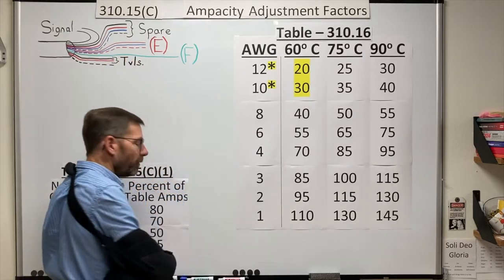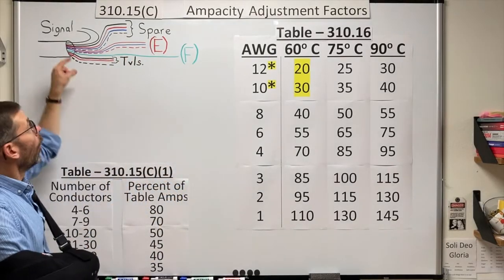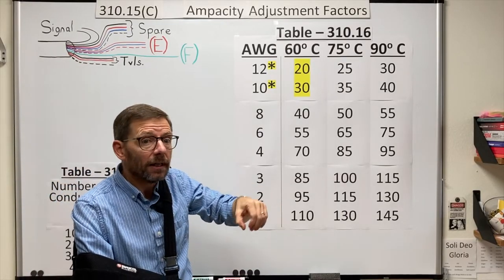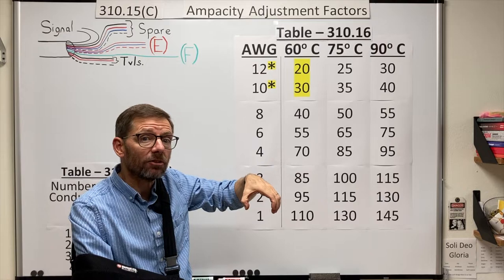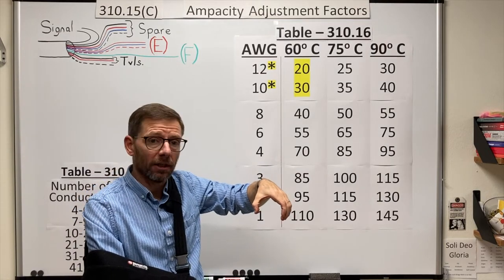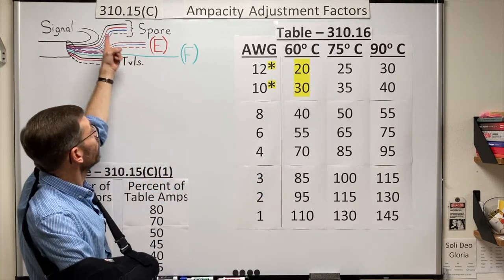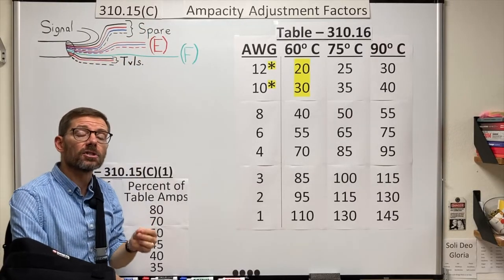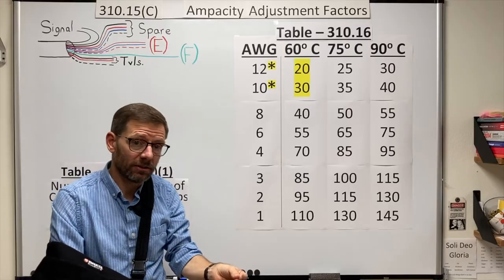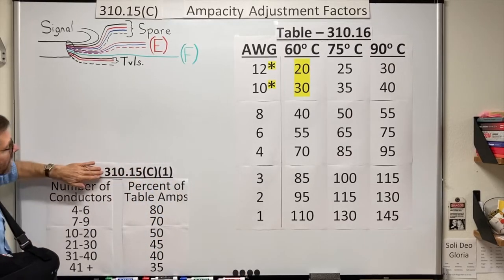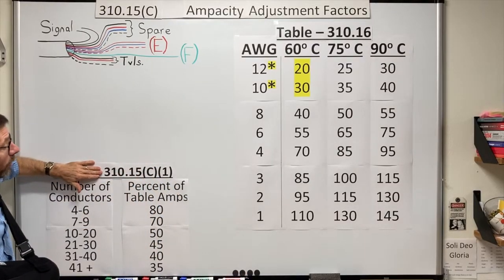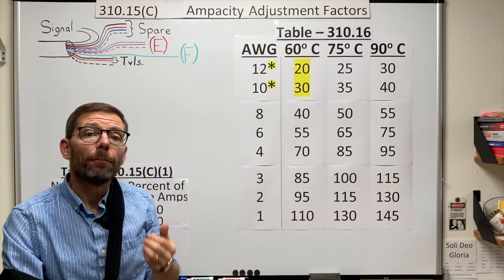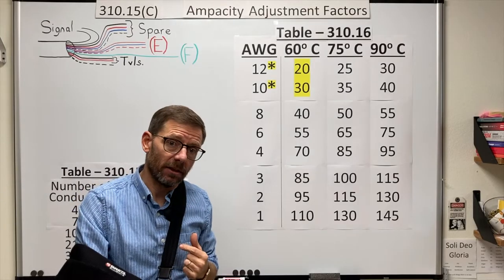Let's clarify a key point. All of these conductors need to be counted when we're doing conductor fill. How big of a conduit do I need to safely fit all the conductors? However, 310.15(C) is just concerned with the conductors that will be adding heat. So in the written section, 310.15(C)(1), it tells me I only need to consider power and lighting conductors.